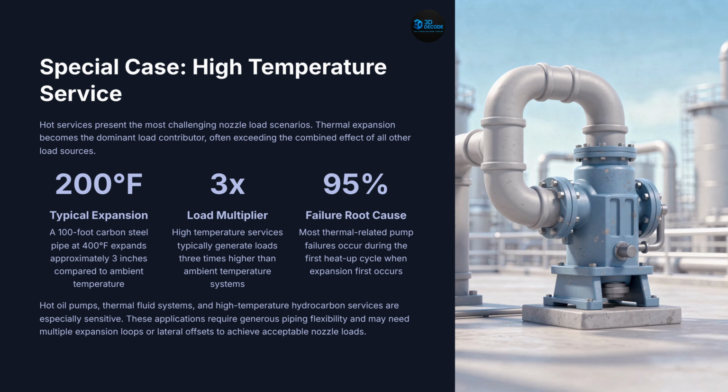Slide 10. High-temperature case. In high-temperature systems, thermal expansion is significant. Pipes can expand several inches. If not properly designed, this creates very high loads on pump nozzles. This is why flexibility is critical in hot services.